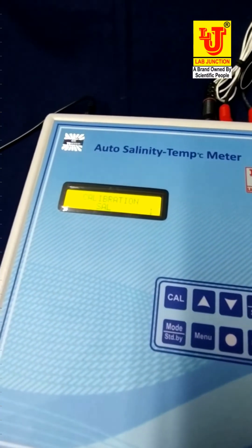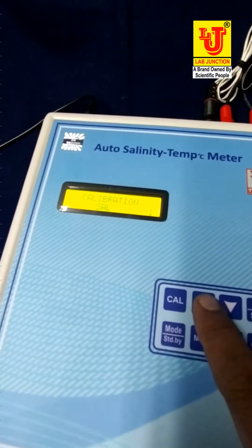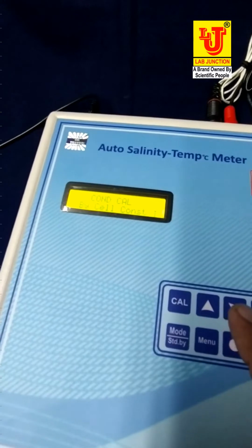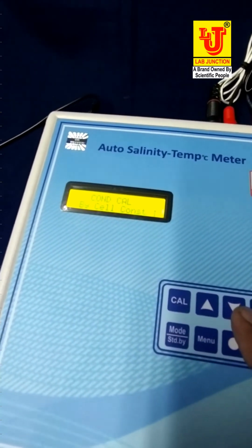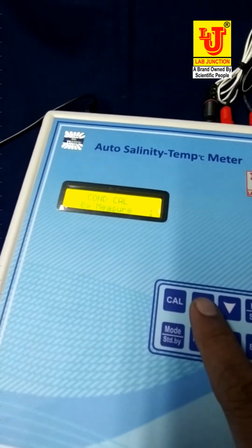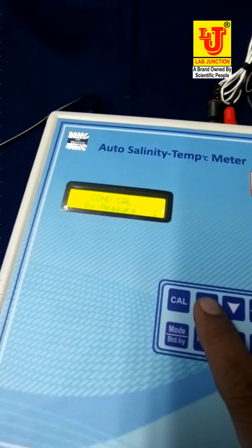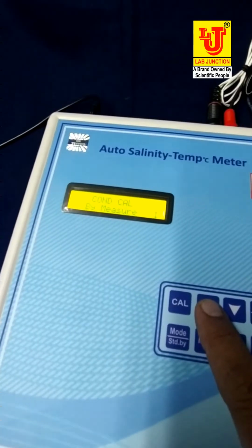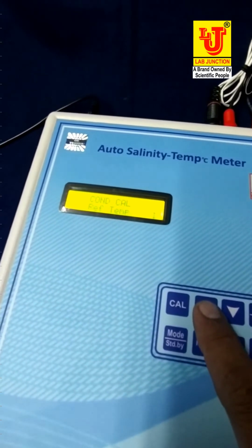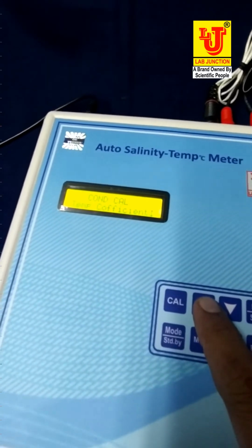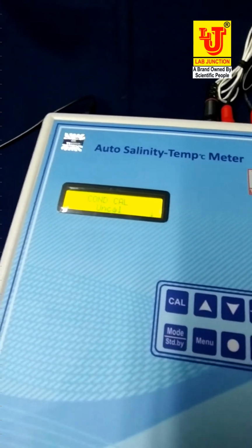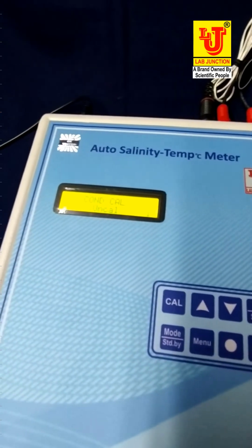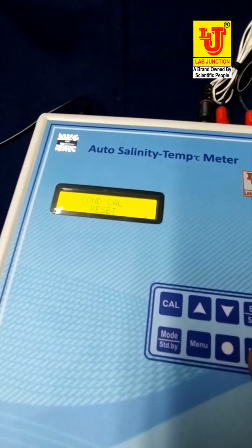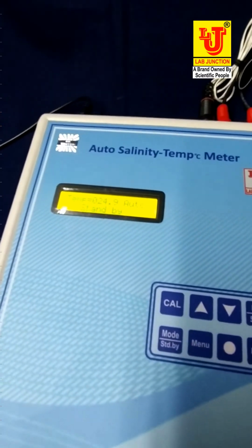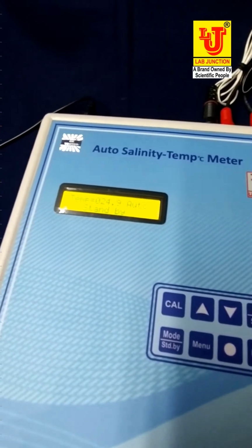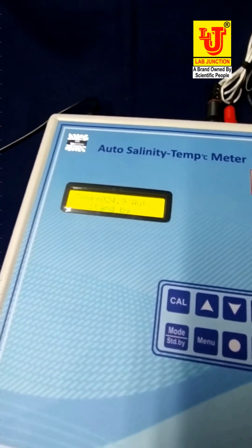This is salinity. If you want to calibrate salinity, press enter on this. Now in this option, if you want to calibrate by cell constant method, in this option, by measure method, if you want to calibrate by known salinity standard. Now up, this is reference temperature. Again up, this is temperature coefficient. K factor. This is uncal. If you want to uncal this instrument, then on this option you have to press enter. Instrument is reset. You do this option when you face some troubles in your results.